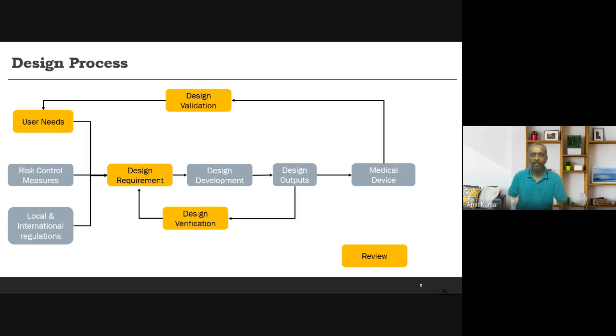In some cases you may find a particular standard which defines all the requirements at a very high level. If a certain safety aspect of a device has to be captured as part of regulation, then it is captured here. But primarily, the safety aspect of the device is captured via risk control. So we take all those things and convert them into design requirements.